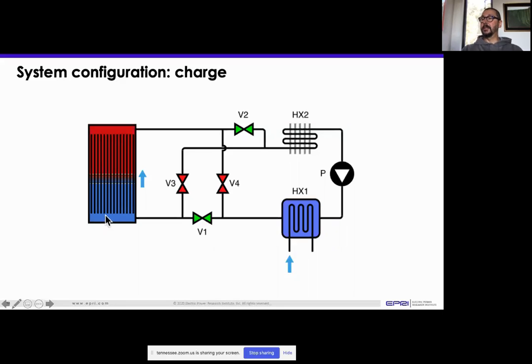This is cold heat transfer medium, so it's a glycol water mixture. It flows through these black lines. These are the ice bags, and it starts freezing them from the bottom, so the freezing front moves from the bottom up. The heat medium warms up as it contacts the water and freezes it into ice, then goes through a heat exchanger.